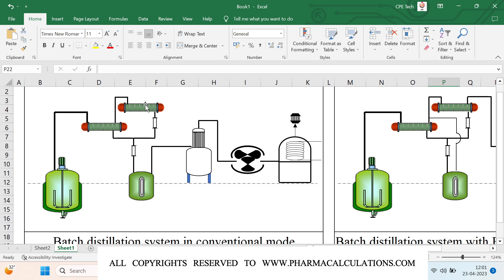The uncondensed vapors then flow into the secondary condenser. The distillate flows through the common collection line and enters into the receiver. While the distillate condensed in the condensers flows from the condensers into the receiver through a straight collection line, a pressure is generated due to the positioning of the condensers at a higher level compared to the receiver.